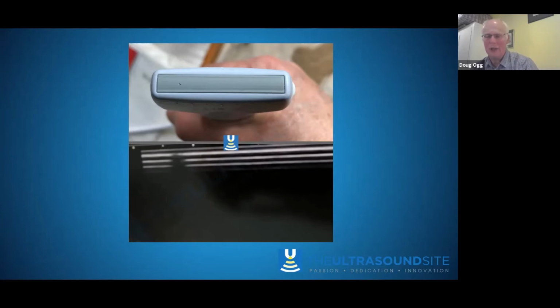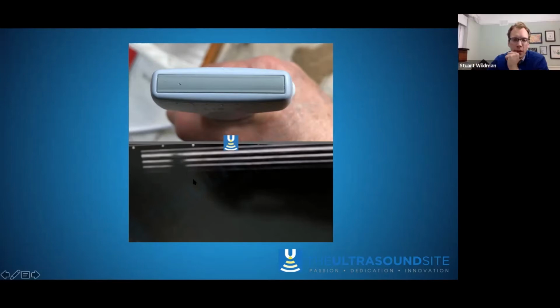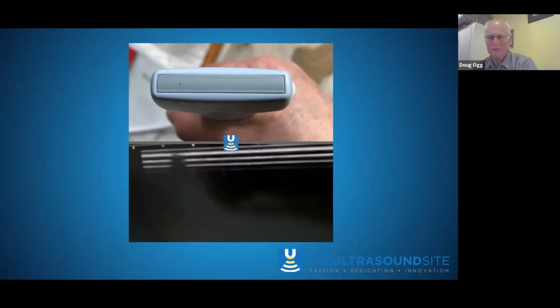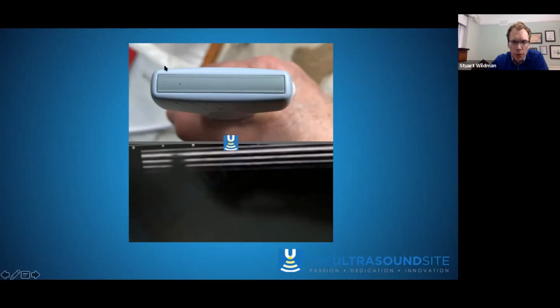So you can sometimes, I've had this in the past where a patient being scanned has said, "Oh, that tingles," and that's a sign that the probe is no longer electrically safe. Because the voltage is quite large in transmission, and that voltage is leaking out from the probe through the gel onto the patient's skin. And this area here is obvious in that image, isn't it? But when you're doing a live scan, grayscale image, that can sometimes be less obvious to less experienced eyes. And so this is why it's so important to check these kind of things.